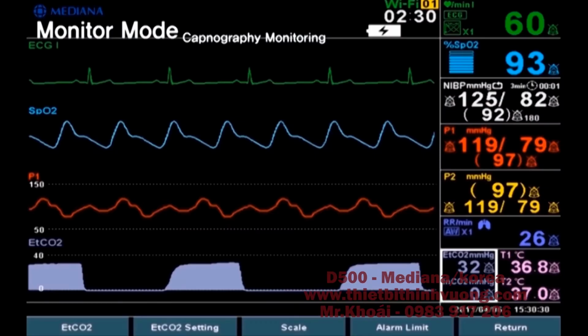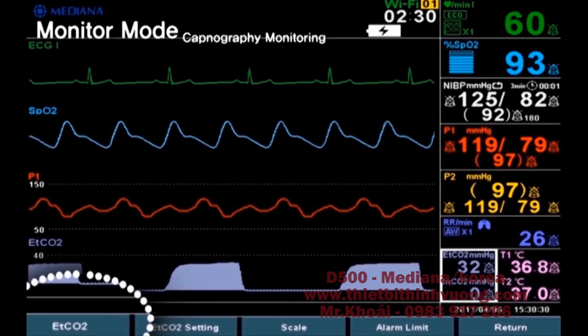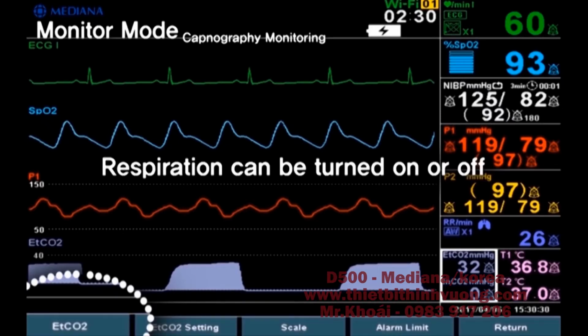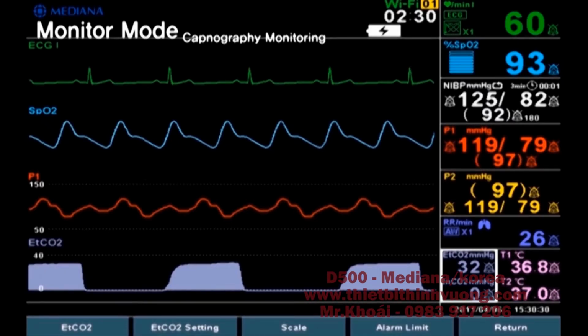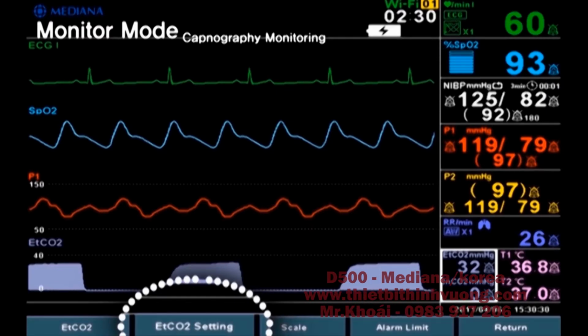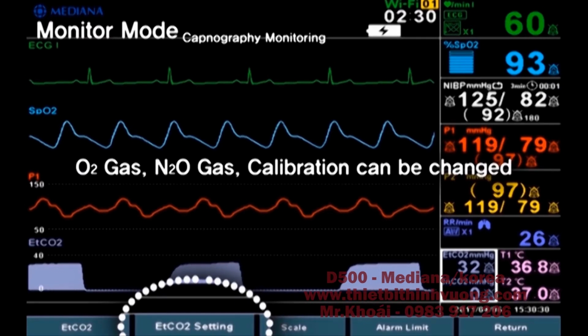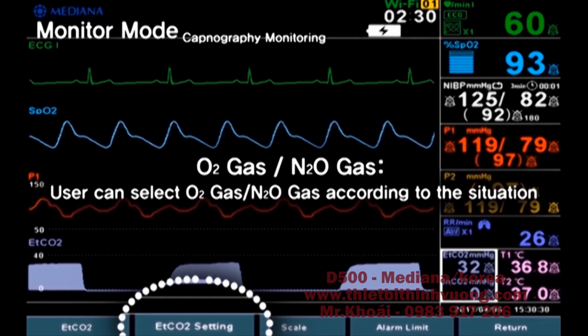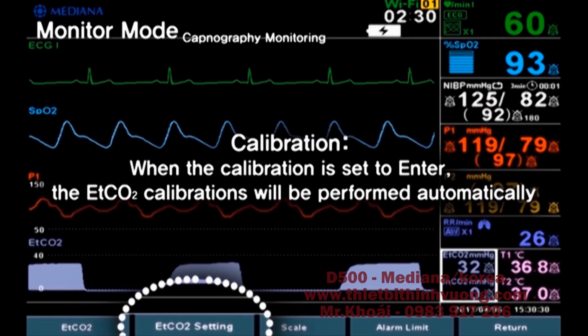Here are the options of the ET-CO2 menu. Number 1. In ET-CO2, respiration can be turned on or off. Number 2. In ET-CO2 setting, O2 gas, N2O gas, and calibration can be changed. O2 gas, N2O gas: the user can select O2 gas or N2O gas according to the situation. Calibration. When the calibration is set to enter, the ET-CO2 calibration will be performed automatically.